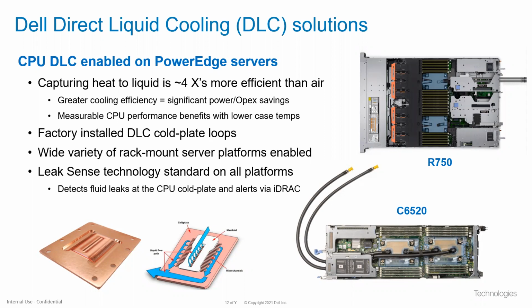If you have Open Manage Enterprise through Dell, you would have a high degree of control over what you do with that signal other than the simple iDRAC alert. Customers could pre-configure the node through OME to either shut down the node or to maintain operational status and alert somebody to come and inspect the node before it gets shut down.